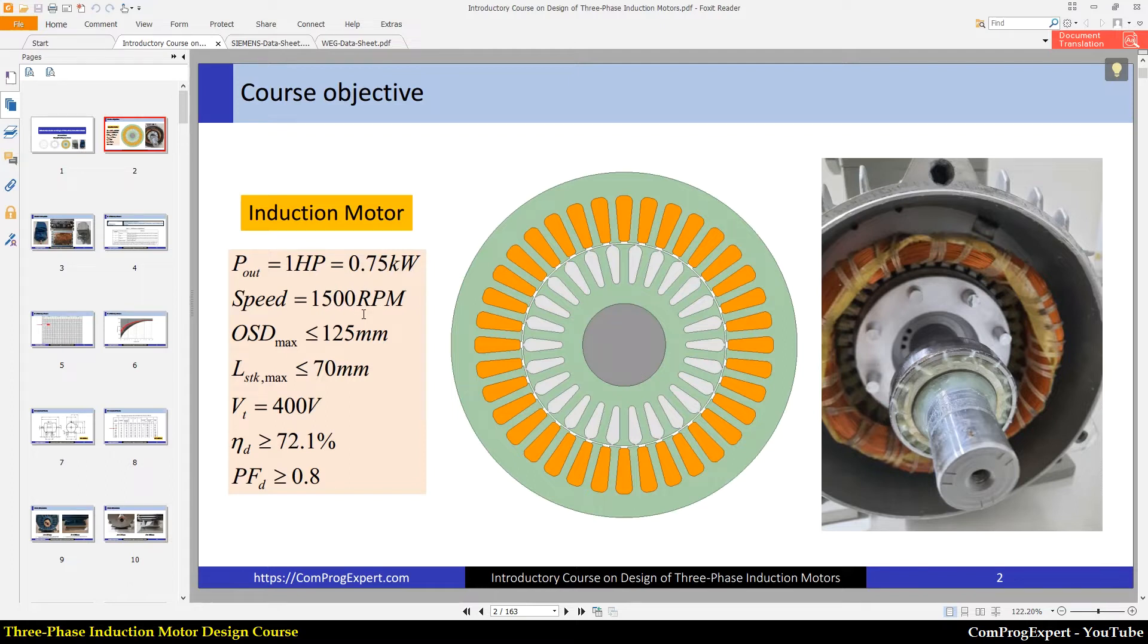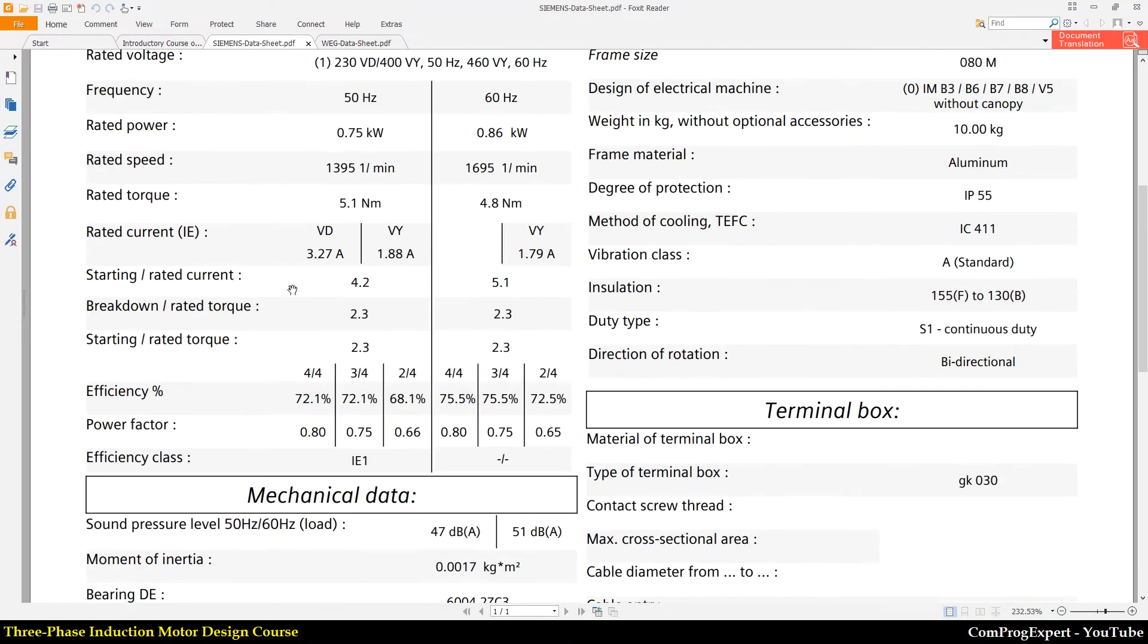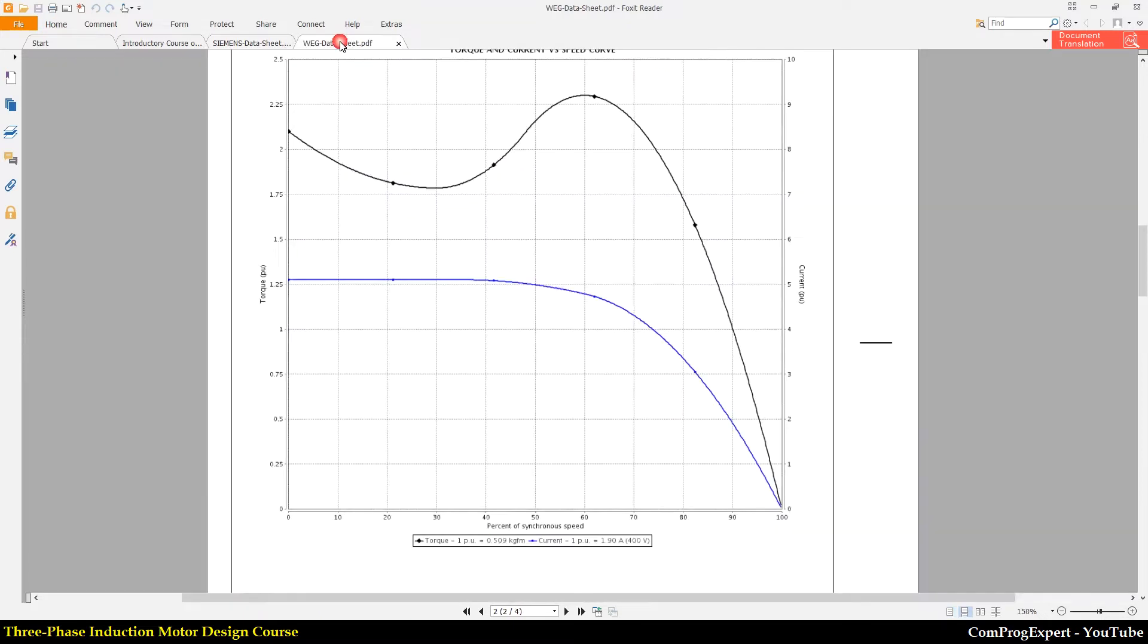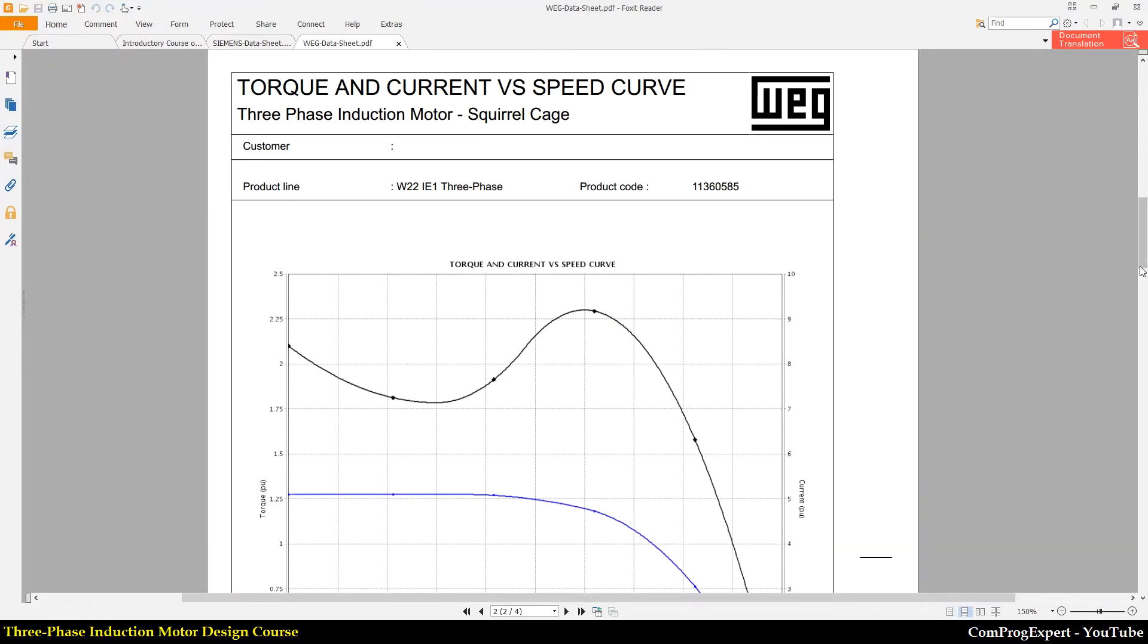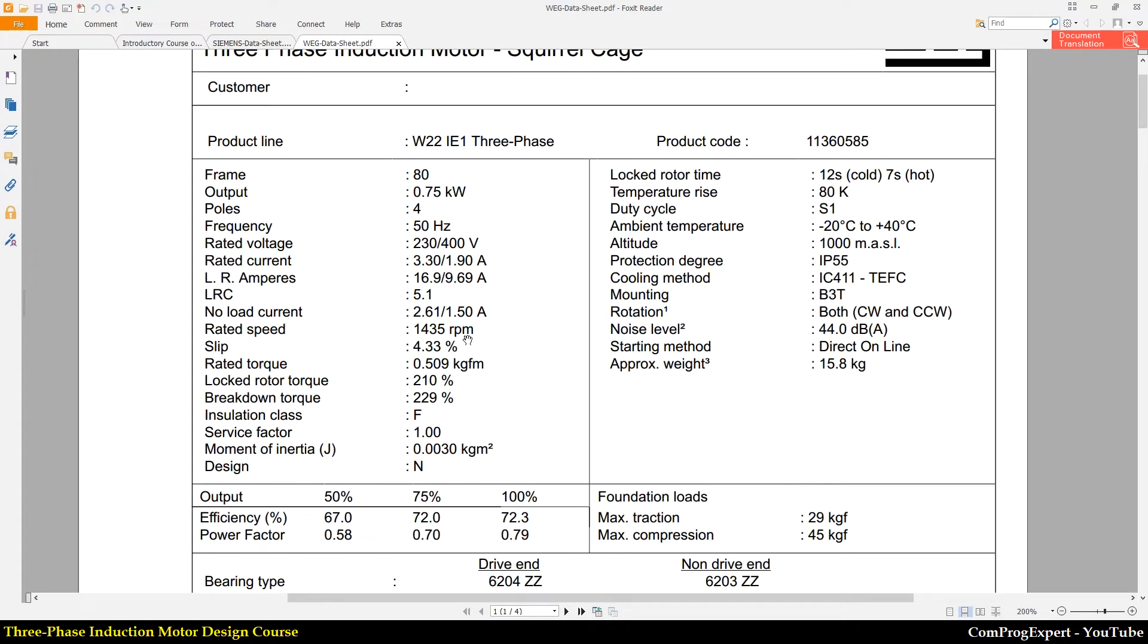And also, because of slip, we have a lower speed. The steady state speed of the Siemens motor, when we excite the motor with a 50 Hertz supply is 1395 RPMs. And also the steady state speed, the rated speed of the WEG motor is 1435 RPMs.